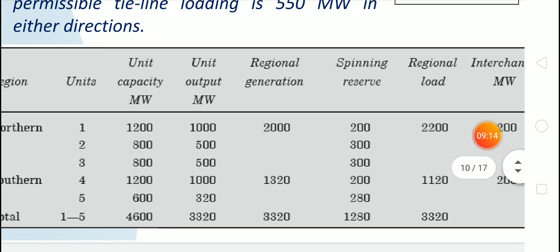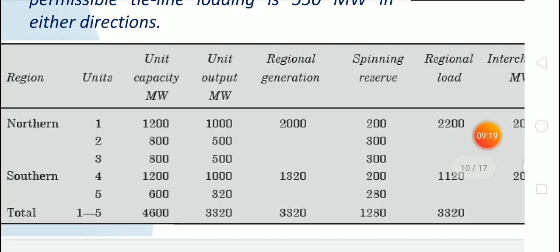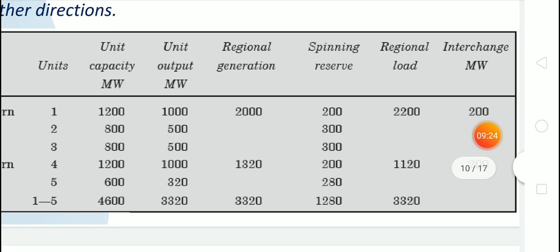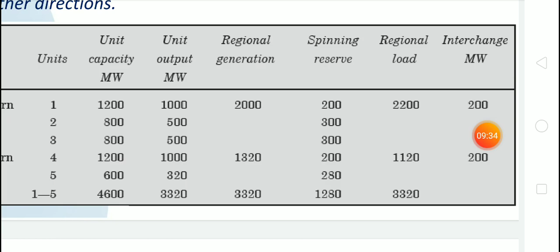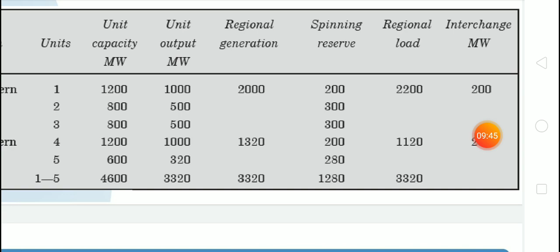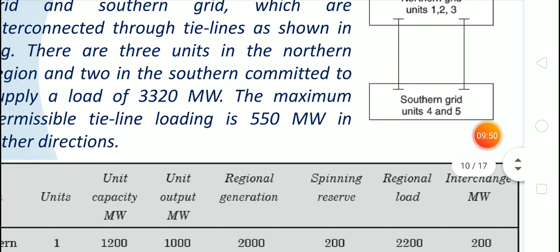And in the southern grid, there is a total generation of 1320 and the load is 1120. So there is a surplus of 200 megawatt, and this 200 megawatt is given to the other grid. So the interchange is 200 megawatt from the southern grid to the northern grid. And there is a spinning reserve of 1280 megawatt in total for both the southern and northern grids.